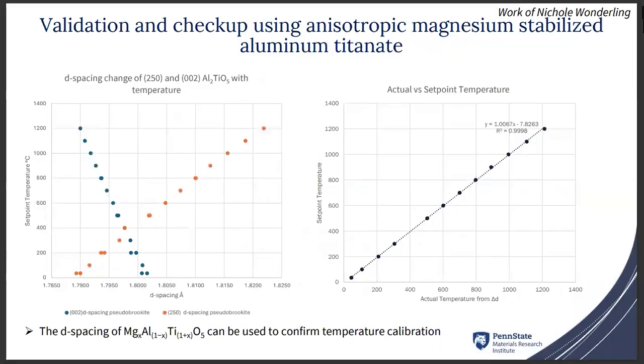In order to validate these results, which is very important, Nicole did this work with other laboratories. They used a magnesium stabilized aluminum titanate material that has a specific d-spacing change between the 250 and 002 diffraction peaks. The study of this change across temperature can be compared across labs. We can see at this point the actual versus set point are pretty accurate, because the accessory was new. But this is a good method to verify that your accessory did not drift over time.